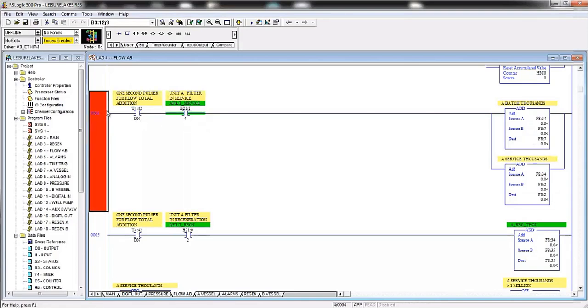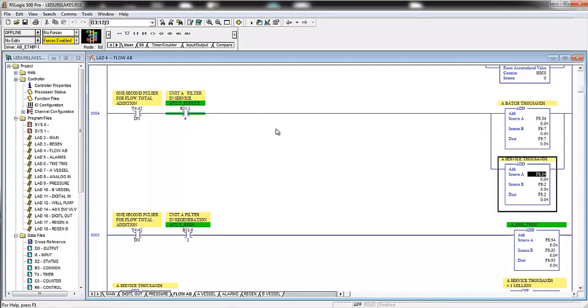And remember, it's going to run through this whole program in about 6 milliseconds. So if these two are true, it's going to do these things, scan the rest of the program, and come back around. And in that 6 milliseconds, maybe something has changed in the process or in the memory registers, and for whatever reason now, maybe one of these isn't true anymore. So the next time it scans, it won't do these things, and it'll just skip down to 5.